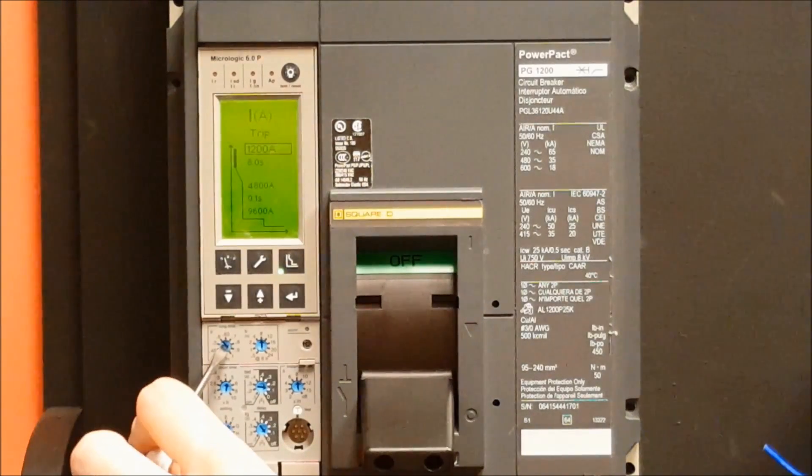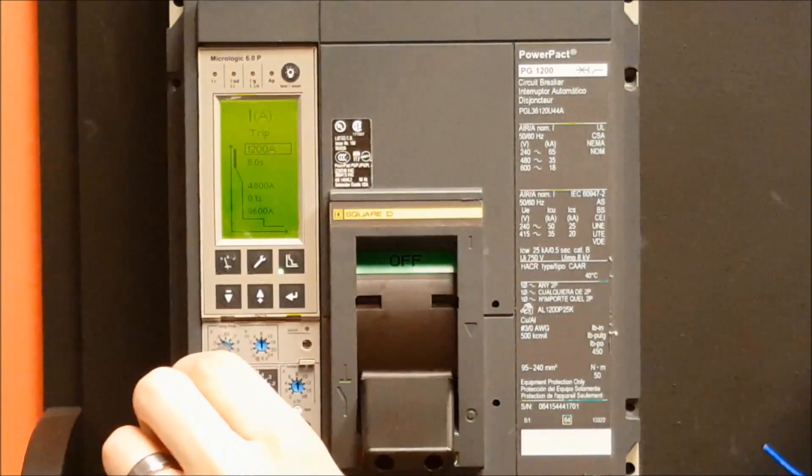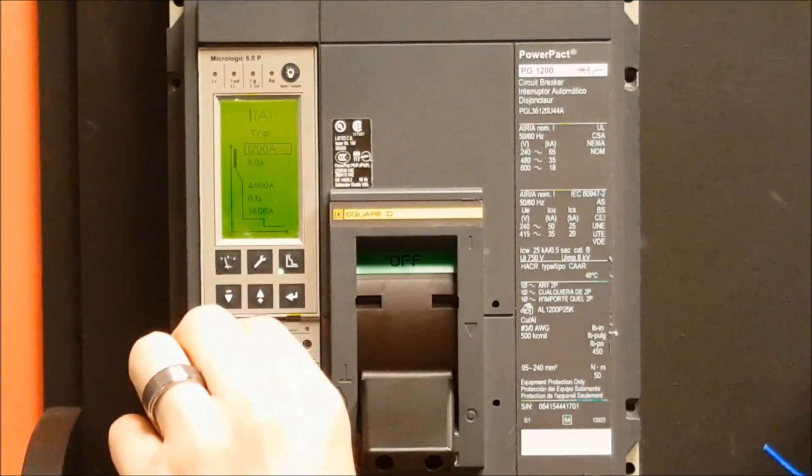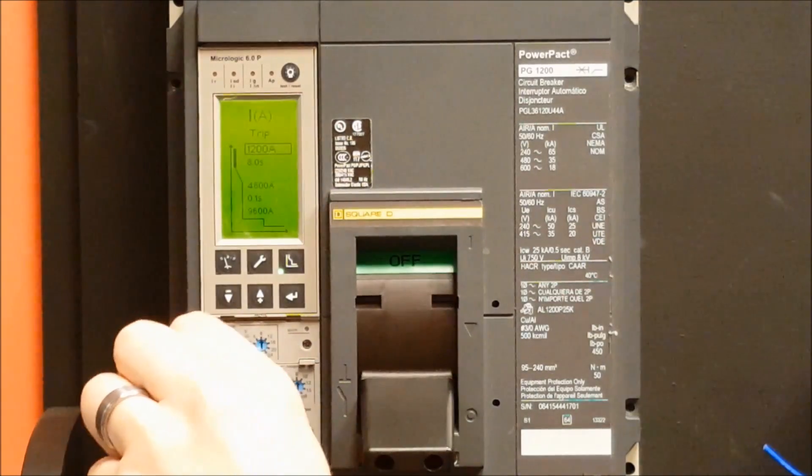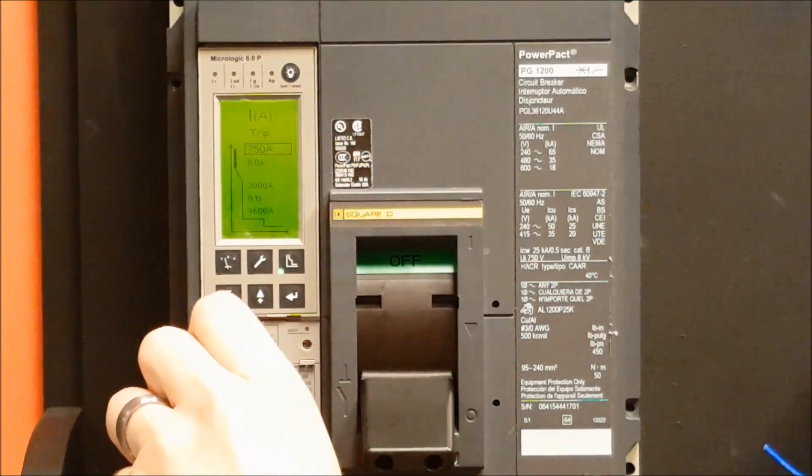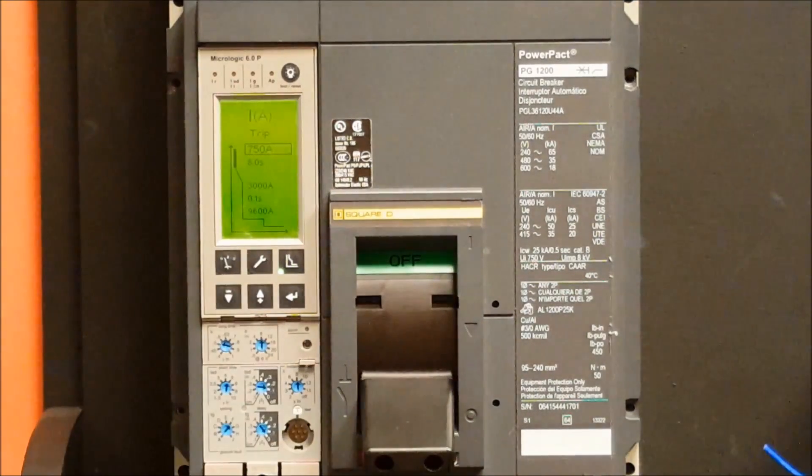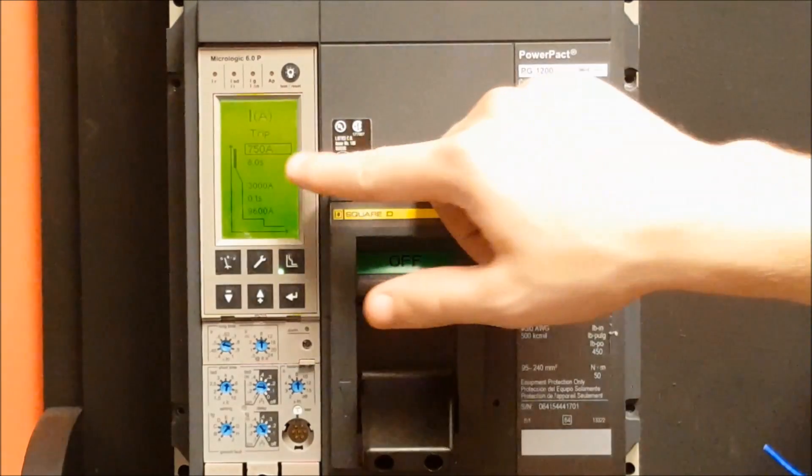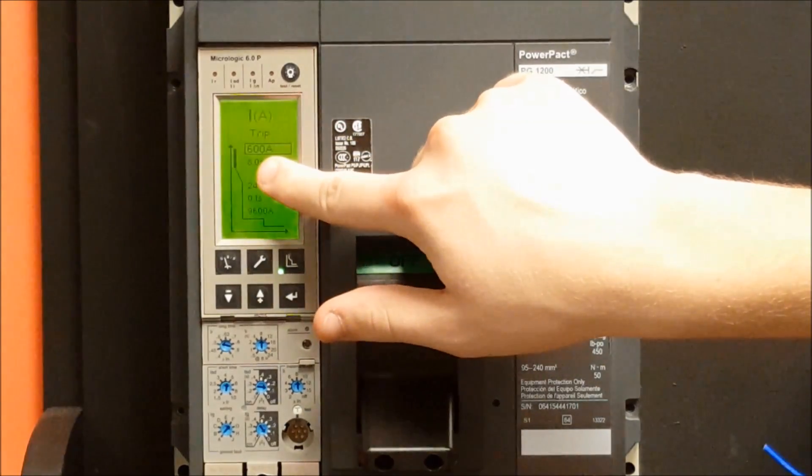For example, if you would like to change the long time setting to 600 amps, you would change this dial to point at 0.5 and you'll see that the amperage value changes on the screen.